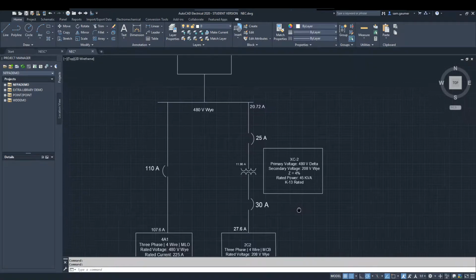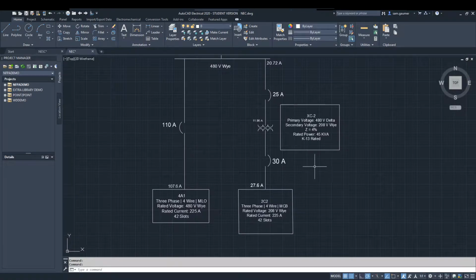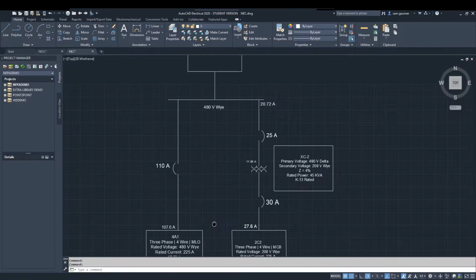Starting with the NEC project, I was able to find some panel boards that met all the specifications, rated at 225 amps each. That meant there's no way they're going to blow, since the rated currents we calculated were 107.6 amps and 27.6 amps, so that's perfectly safe.